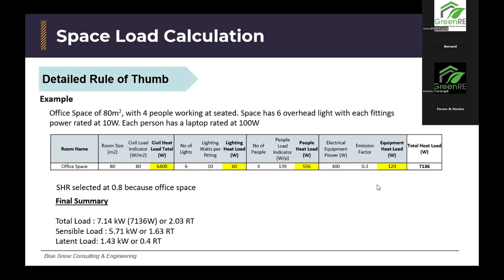Okay, the room size and the civil load, that's your calculation, you just multiply the two. Then the number of lights times the watts per fitting. Since it's 1 to 1 for lighting, it's 60 watts. For people load, you need to refer to the standard. What is the value? Because if it's a gym, then it's a totally different number, because people are working out, there's more sweat, there's more moisture. And the last one is the emission factor. Since these are laptops, it's 0.3. And that's how you get your total heat load. Heat load and cooling load are interchangeable terms.